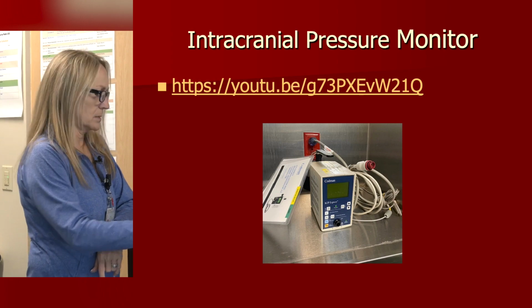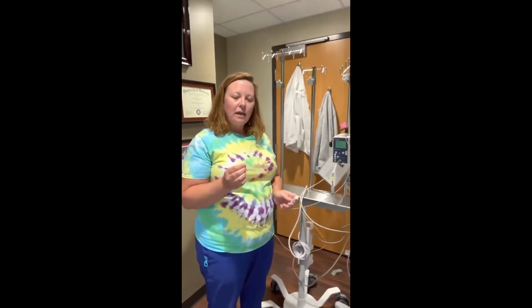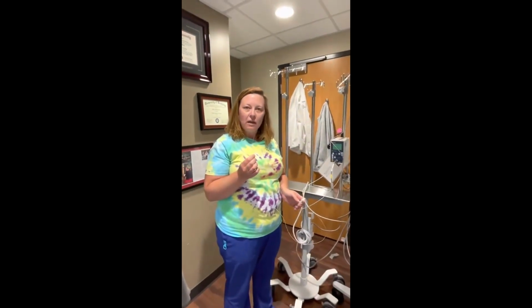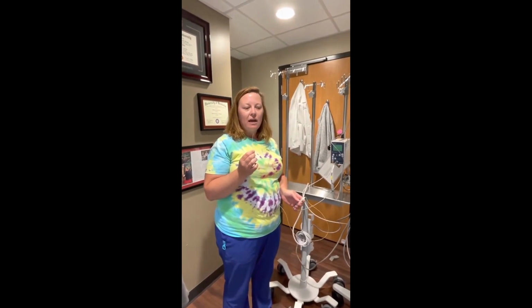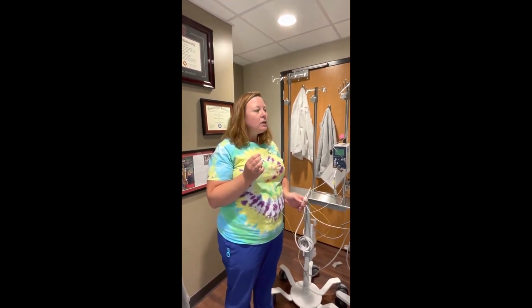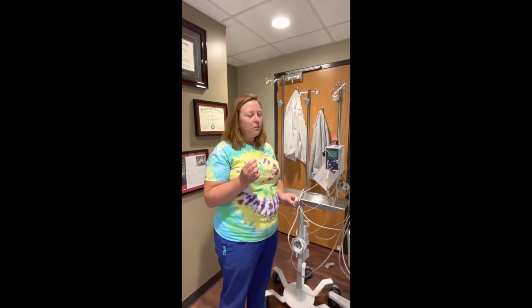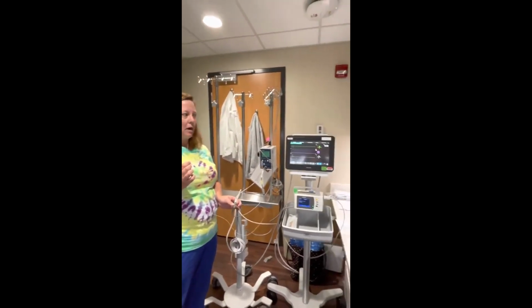So let's try that. This is our new Codman catheter that we are going to be receiving. There's two types of catheters that we will see. We will have one that will be our bolt, but we also have the capability now to have a tunnel catheter with our EVDs. What you will need to know about these is that they are MRI compatible, meaning that we can take these down to MRI, but we will not be able to monitor while we're in MRI.